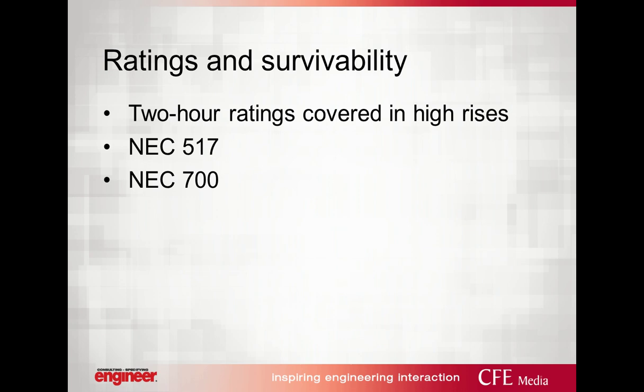Thanks. So in 700, 710D, there's 4 specific items, and I'm going to concentrate primarily on equipment and feeders. Specifically, the code says that as long as you're allowed to run feeders and put equipment in spaces that are within a sprinkler's capability, so if you have sprinklers in a space and that equipment and feeder are directly under the spray of that sprinkler, it's okay. You can put it in that location. However, if you're in a building that has sprinklers and you're routing that feeder above the ceiling where there's no sprinklers, that's not in compliance.